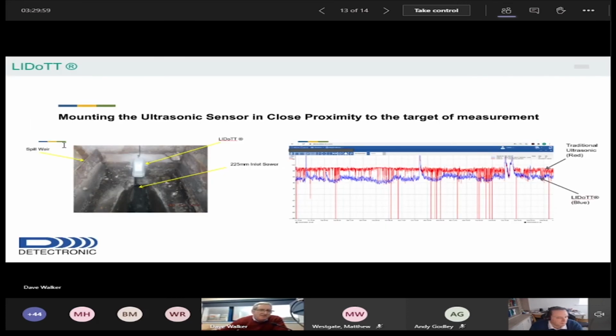So, mounting the ultrasonic level sensor in close proximity to the target of measurement. We've got a comparison graph there. The red line is the traditional ultrasonic level sensor, and the blue line is where we've mounted the sensor in close proximity to the target of measurement. As you can see there on the level, the ultrasonic level is below the spillway at that point, but within close proximity. The advantage, which Andy Godley touched on earlier in his talk as well, is that we're still able to pick up that valuable data in dry weather conditions.